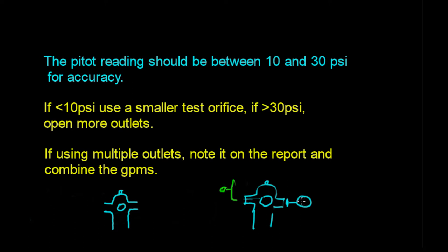So you get your static pressure, then you'd open up your valve with your play pipe here. Once you've flowed for a minute, you've got clear water, and your residual pressure stabilizes, then you would read this hydrant and just note that it was one fire hydrant where you put your gauge and Pitot. Now, say you have multiple fire hydrants.